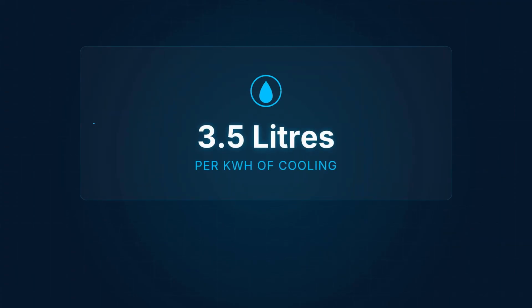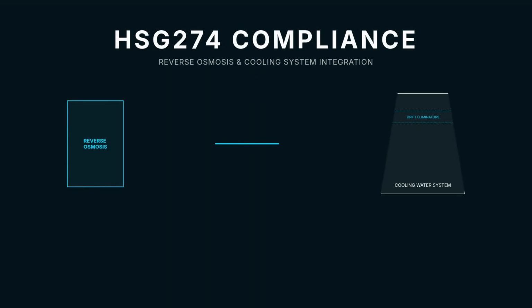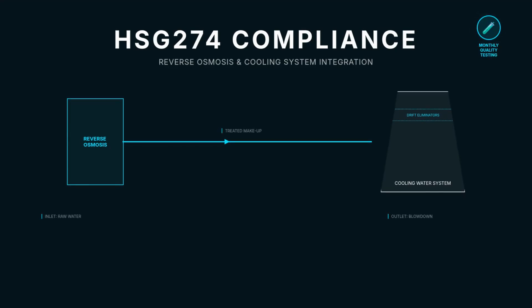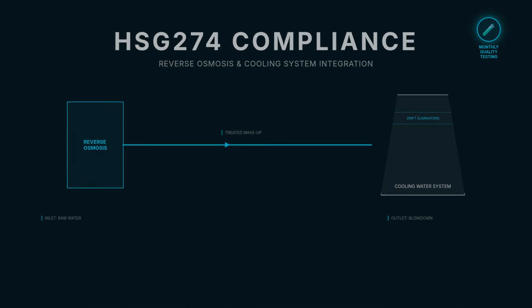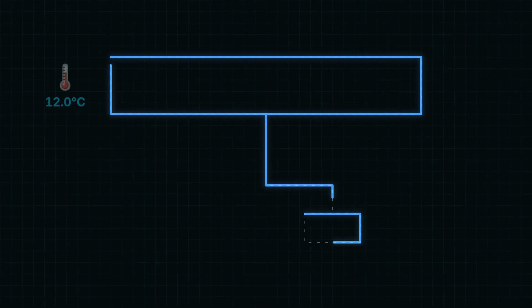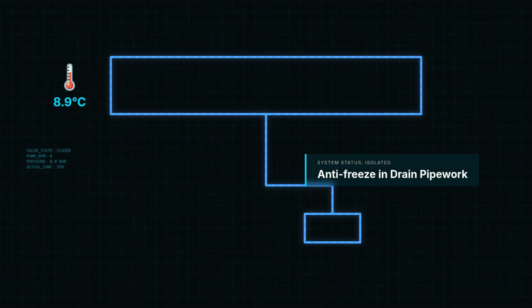We consume approximately 3.5 liters per kilowatt hour of cooling delivered, with every single liter metered and reported for our monthly sustainability auditing. Safety and maintenance are critical. We use reverse osmosis to prevent hard water scaling on the nozzles, while drift eliminators and monthly quality testing ensure total compliance with strict Legionella safety standards. Finally, the system is isolated and drained when outdoor temperatures drop below 3 degrees. Antifreeze on the drain pipework ensures the infrastructure is protected from frost damage during the cold winter months.